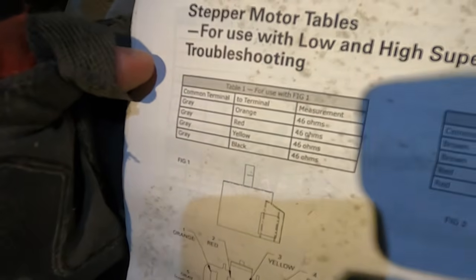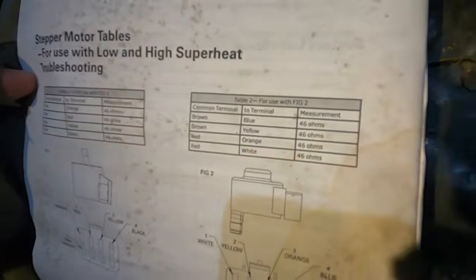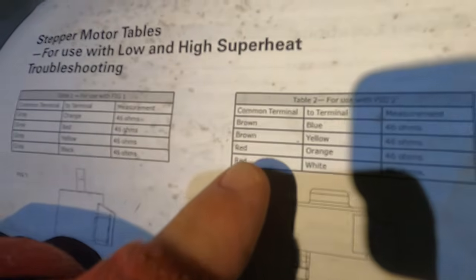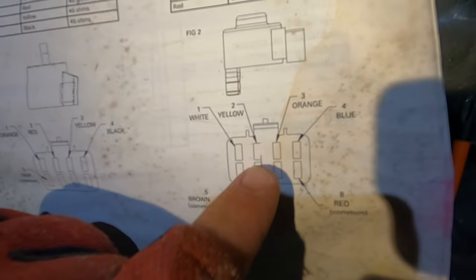This is the ohm chart, ohming these things out, and this is the one I've got. So basically both of these are going to ohm to 46 ohms. When you're testing them, you just got to make sure you're using the right chart and identify the right stepper motor that you have in place. We are using this one. So basically what happens here is I'm going to ohm gray to all the other four wires, and I'm going to be ohming the windings in that stepper motor.